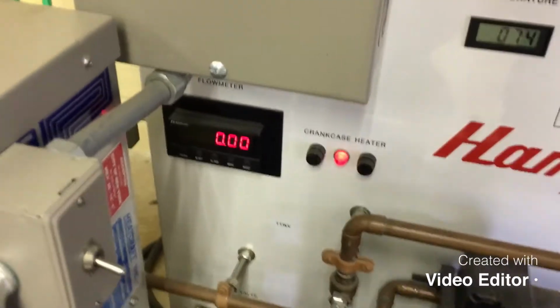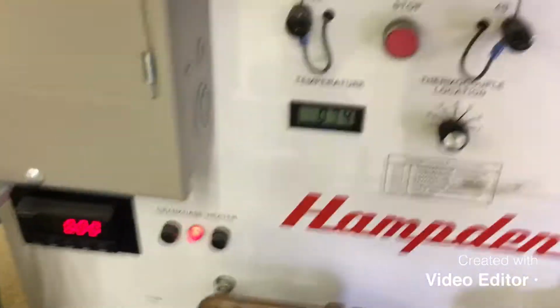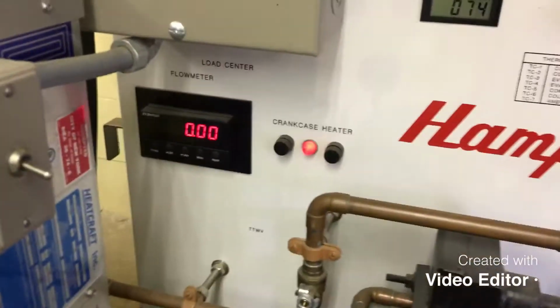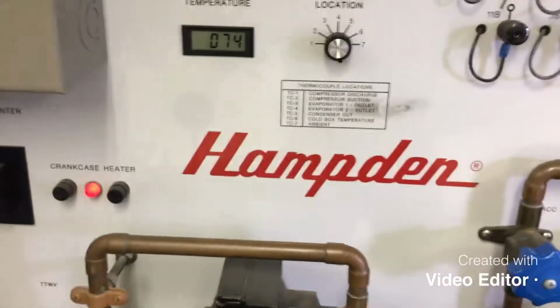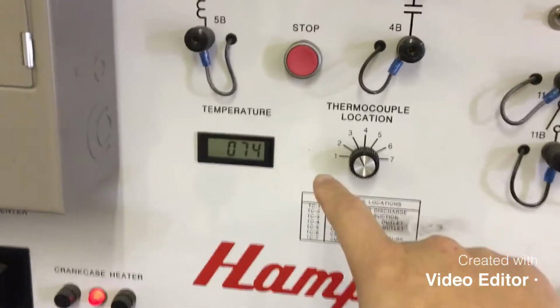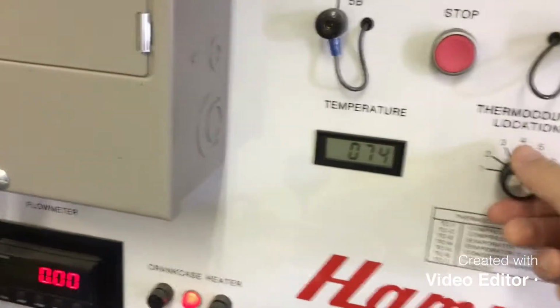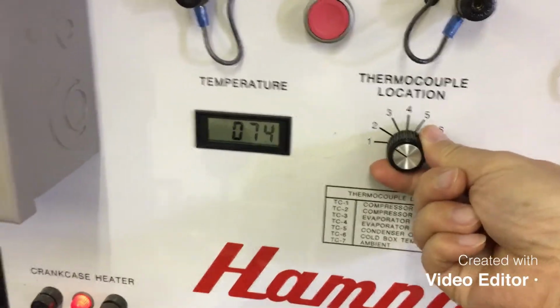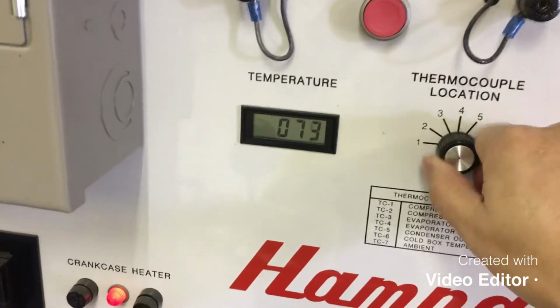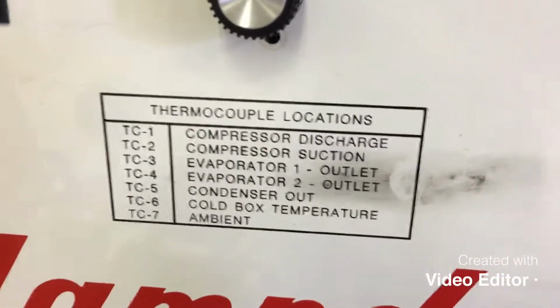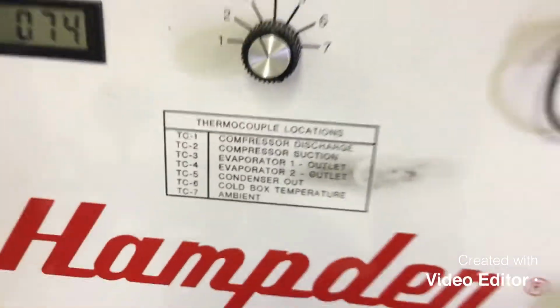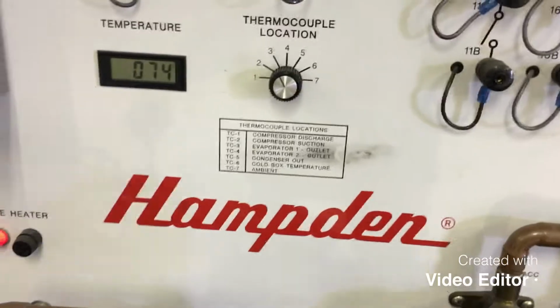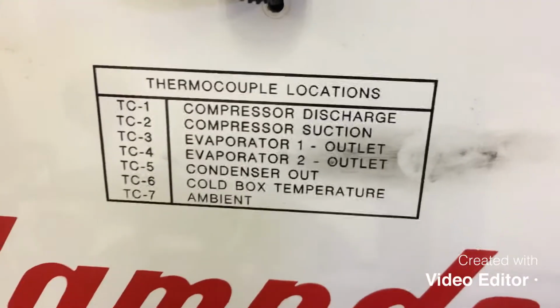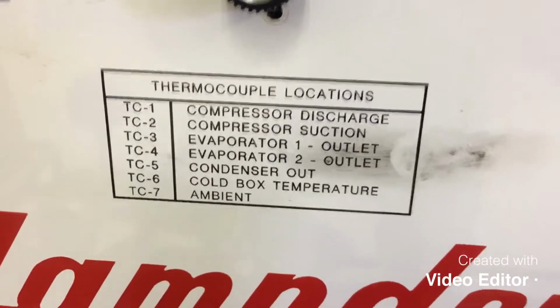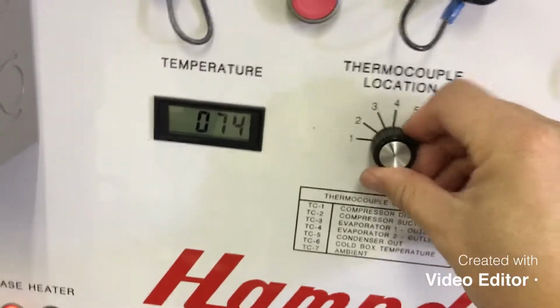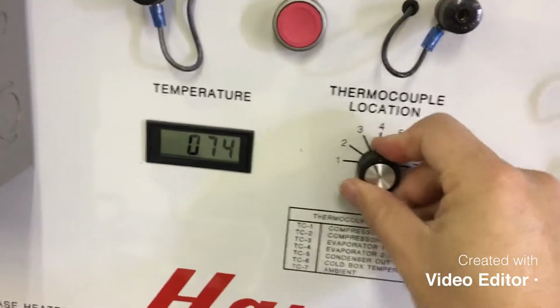Then this is the flow meter. The red one is the flow meter for the water, for the condenser. This panel shows the temperature. We can switch this to show different temperatures at different locations. So TC1 is the compressor discharge, TC2 is compressor suction, and so on and so forth. Every time we switch this, it will show a different temperature here.